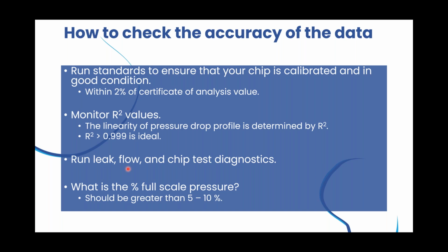So why do we check for leaks on the MVROC2 and Initium, but not for our other instruments? The reason is that for these instruments, the Initium and MVROC2, we have this powerful feature called sample retrieval and recovery. This retrieval and recovery require a closed system.